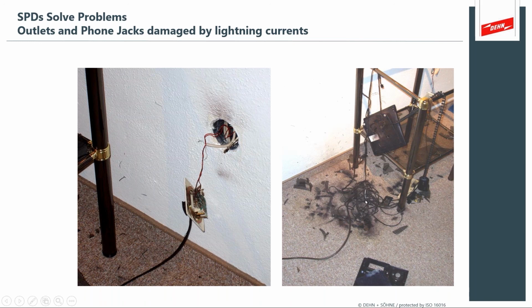We're not talking about main lightning currents. We're talking about smaller currents that still created enough damage to introduce fire hazard into the building. So in both NFPA and IEC, we described the lightning protection system, the external protection with your air terminal, down conductor, and earthing electrode. But all of the standards still dictate that you need to apply surge protection devices to further control the risk of fire. And this is what could result with inadequate surge protection devices. So we talk about feature benefits. Well, you want to have the features in your SPD to provide suitable benefits to provide reduction of fire risk.